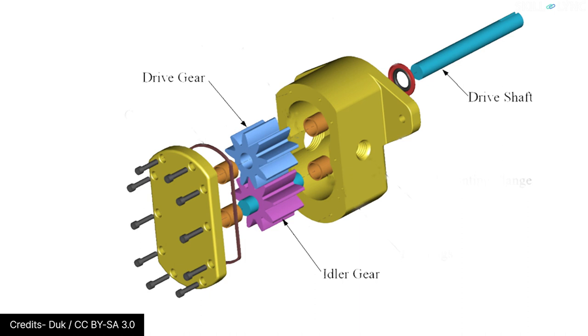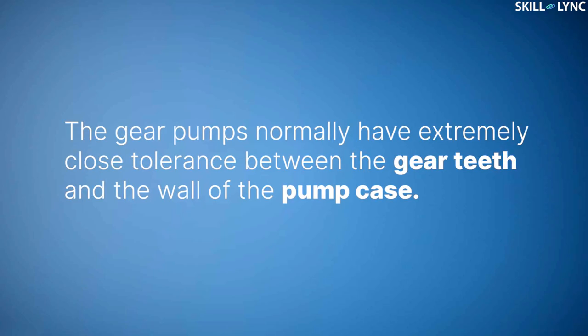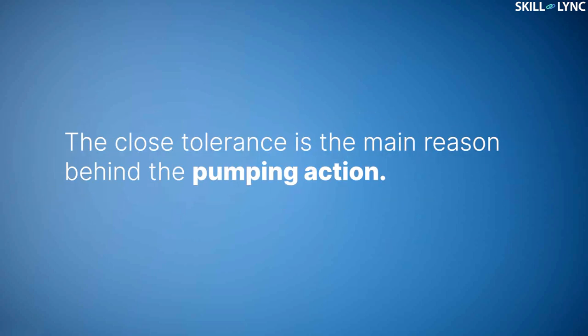The other gear acts as an idle gear and rotates with the help of the meshing action from the driver gear. The gear pumps normally have extremely close tolerance between the gear teeth and the wall of the pump case. The close tolerance is the main reason behind the pumping action.